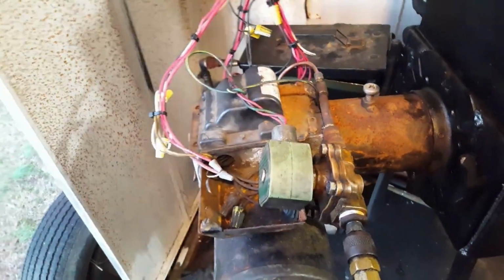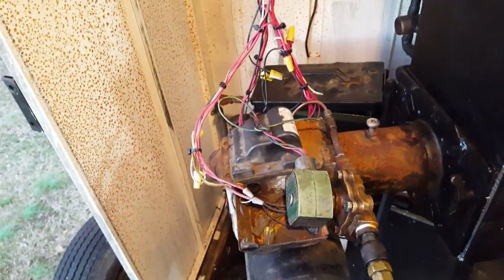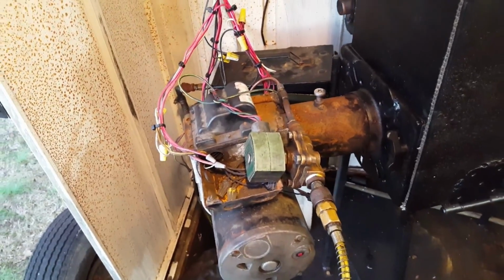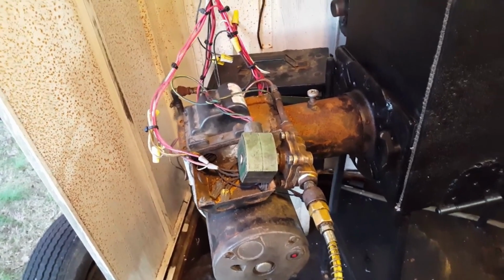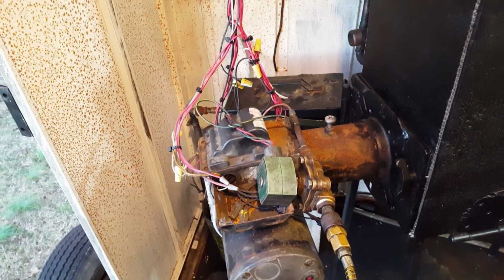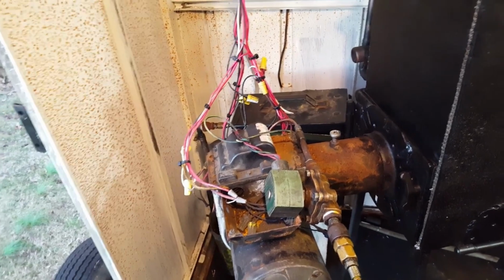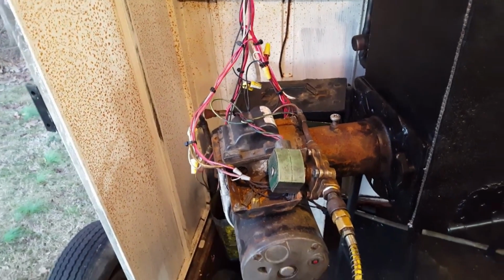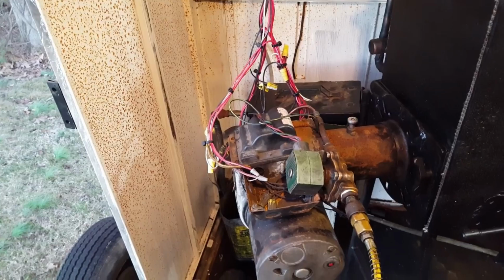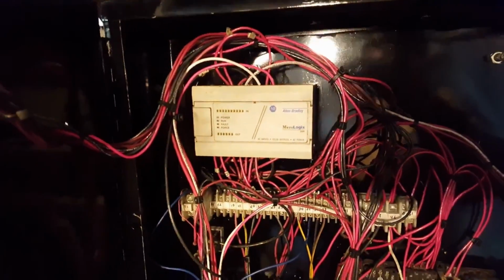Another input is the flame sensor inside of this burner here. I think I've got it set to like 5 seconds. If it doesn't see a flame, it shuts everything down. I could probably go a little longer, and I may do it. It just depends on how well it runs. But if it doesn't see a flame, or if it loses flame, it'll lose the input and shut everything down.